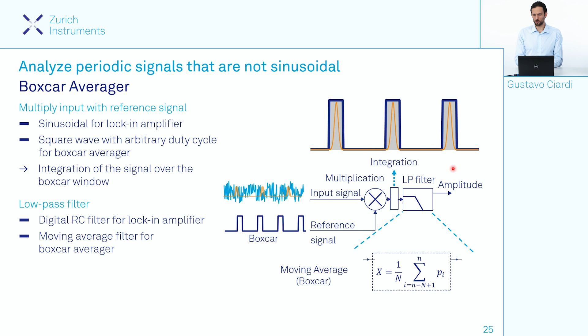As we've seen before, for the lock-in amplifier, we are taking our signal and multiplying it with a sinusoidal reference. In the case of Boxcar Averaging, instead, we are taking our signal and multiplying it with an arbitrary square wave with arbitrary duty cycle. After the multiplication, we have an integration stage where everything under the high time of our square wave is integrated and then sent, again, to a low-pass filter. In this case that is not an RC filter, but rather a simple moving average filter, meaning that a certain number of these integrated boxes are averaged, and the result is then output from the instrument.